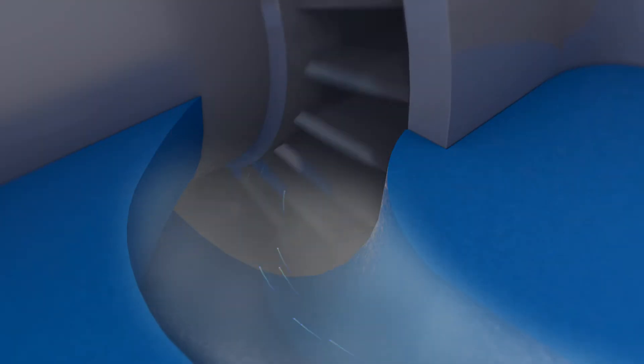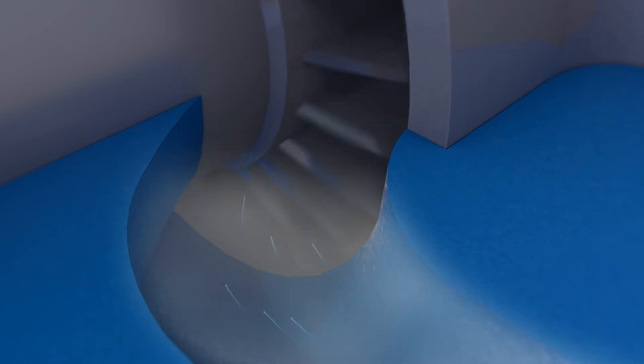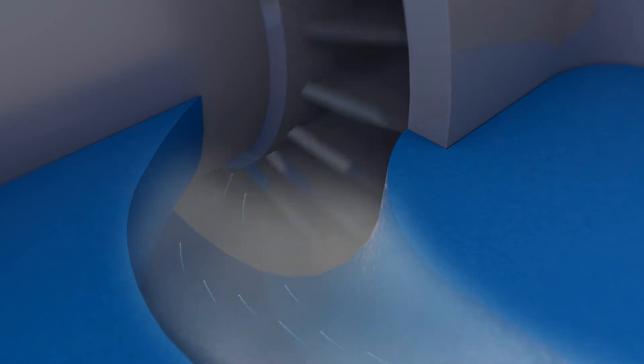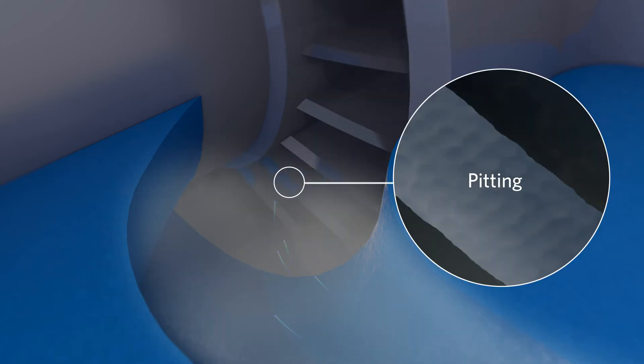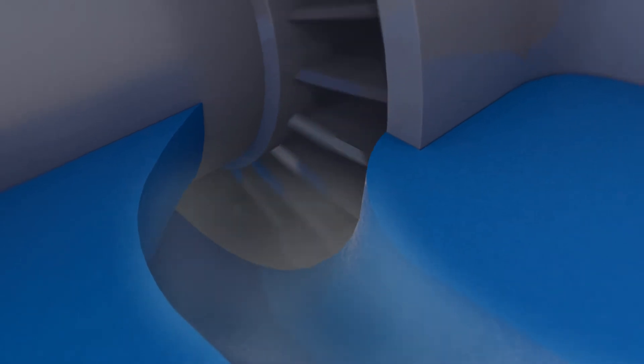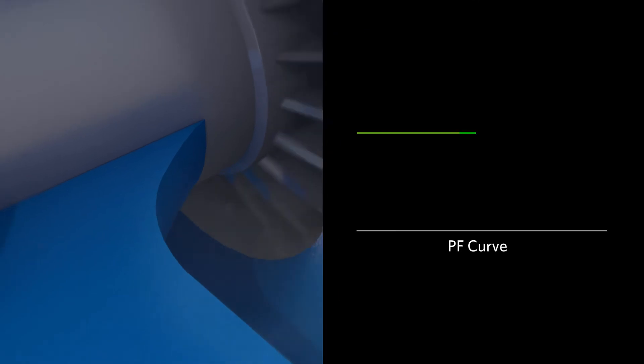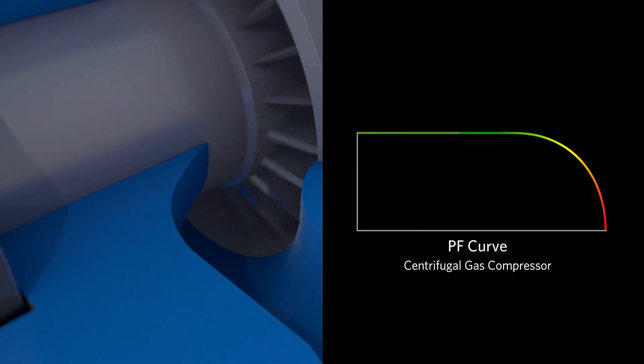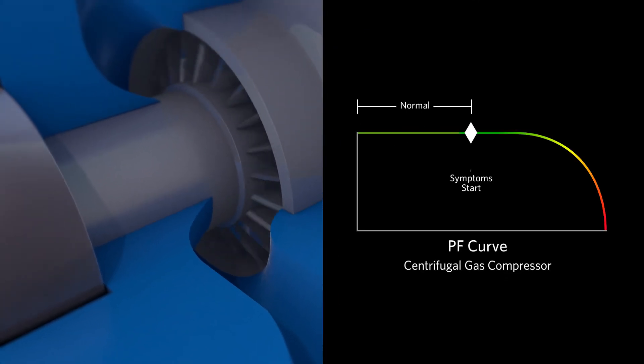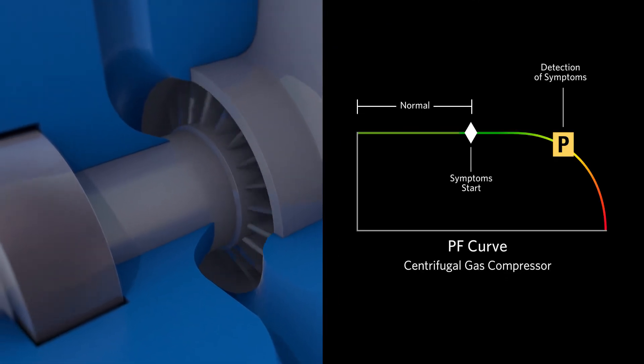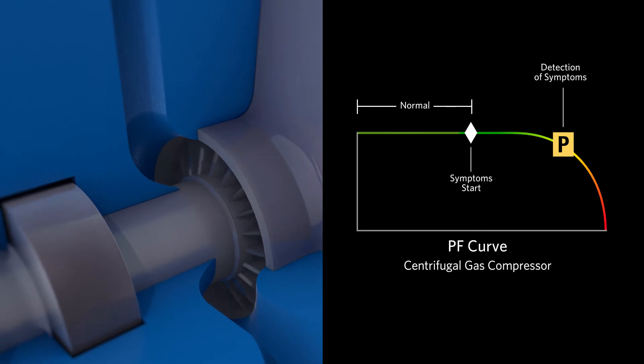Additionally, compressor blades spin at extremely high velocities to compress gas, so the impact of every drop of liquid can cause pitting and deposition. Such microscopic repeated damage over time causes compressor blades to lose integrity, become misaligned, and cause catastrophic failure.